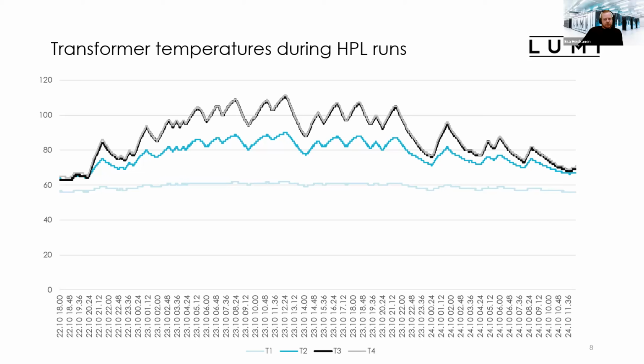These are 3-phase cast resin transformers, and those are static transformers, which means that there are no moving parts. And these are usually a good choice for high service reliability situations. So those are pretty much service free and high availability transformers. In normal operations now with LUMI, the temperatures are somewhere like 70 to 80 degrees. But even with this, it didn't cause any physical issues or any blackouts in the system. Actually, those transformers can go up to 140 degrees before they will shut down the power.